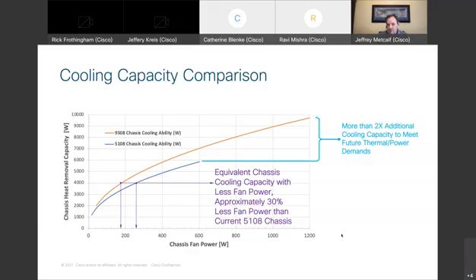And on the orange curve, what you see is about 170, 180 watts of power required by the system fans for the X-Series chassis. And on the B-Series chassis, the 5108, it's more like around 230, 240 watts, basically a 30% reduction in fan power required to cool the same thermal load in the chassis. So again, that's a takeaway of all those things that I talked about earlier. Larger fans spinning at lower speeds, you're drawing the same amount of air volume through the system. Okay, next slide.